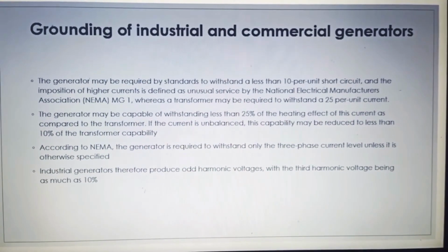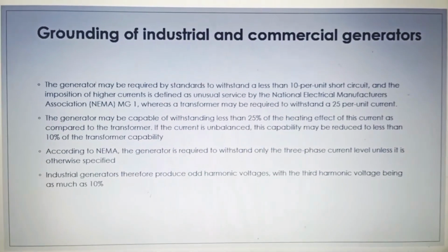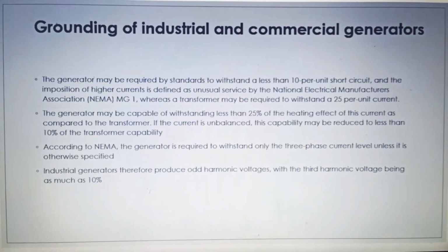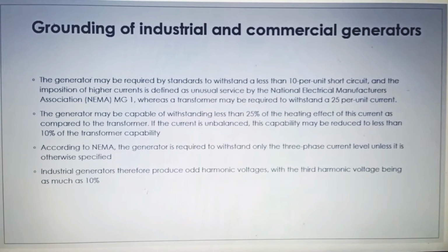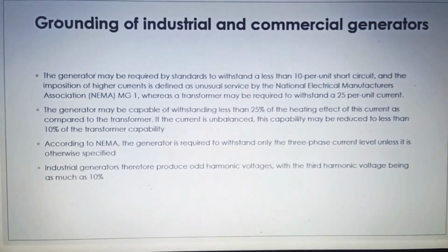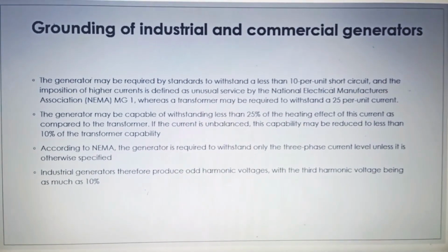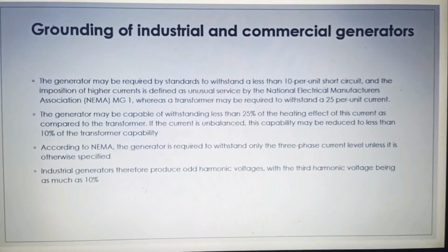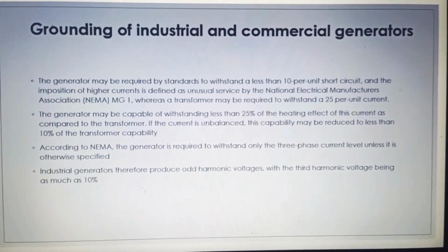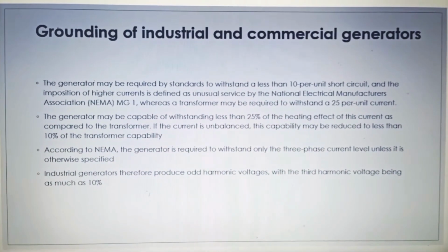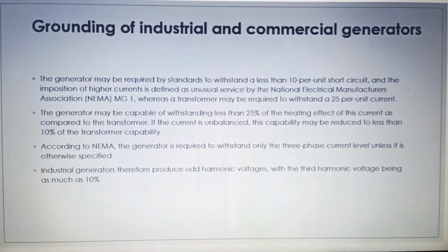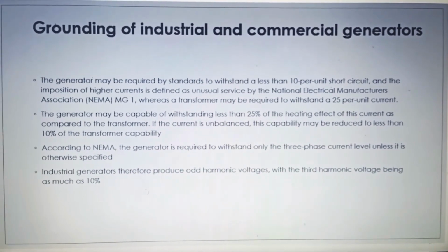With a solidly grounded neutral, the steady-state ground fault current will be about 8 times the full load current, while the steady-state three-phase fault current is 3 times full load current. But because of the negative sequence content of the ground fault current, the generator has less thermal withstand capability than it would have for a three-phase fault.